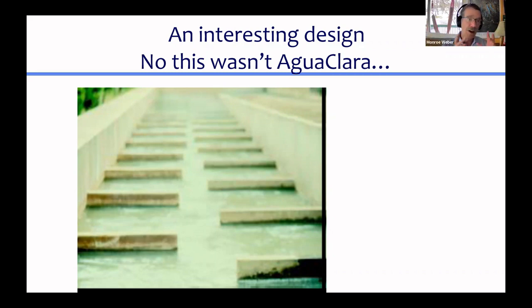And now, even though you might really like it if the water would go around those bends, the water isn't listening to us. The water is doing what's easiest. And the easiest thing to do is to go straight down that channel, right down the middle. And it happily does this. And that is a terrible flocculator. Okay, now you won't make that mistake, right? You will make sure that when you design a flocculator, the water has to follow the path that you want it to follow.